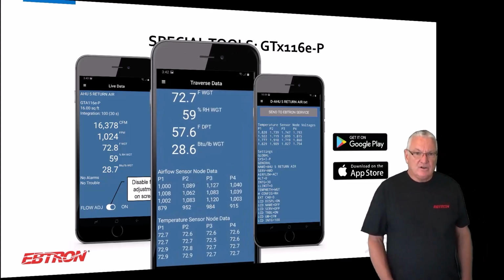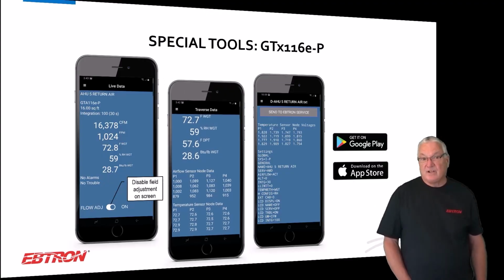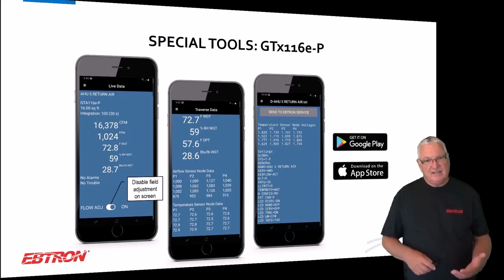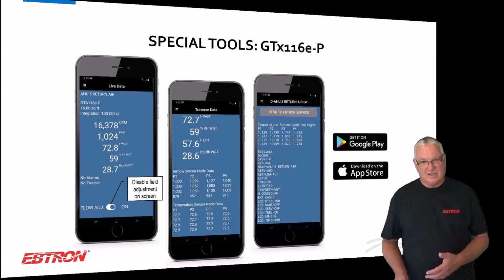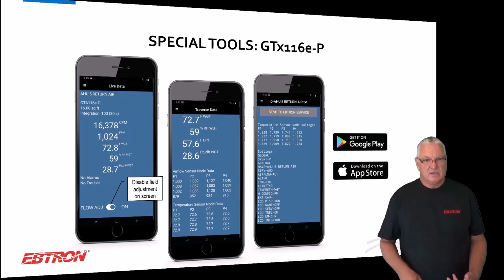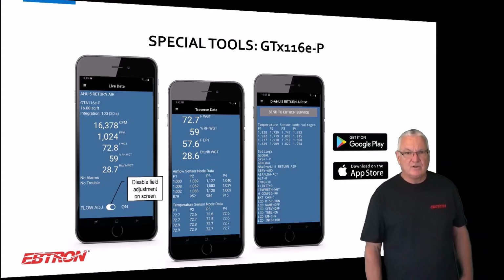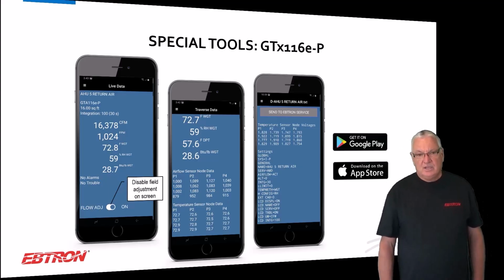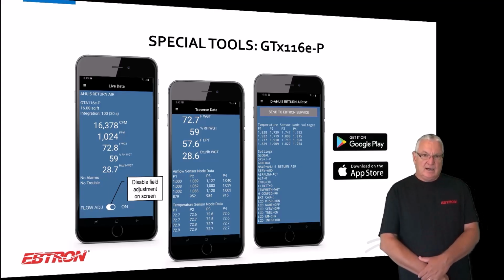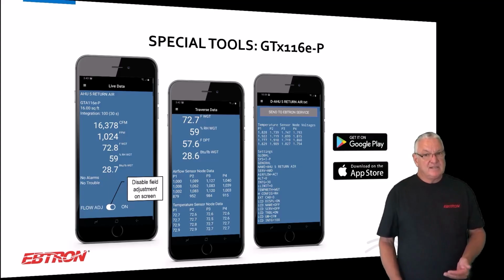Another screen you could go to is this traverse data screen. This was developed for balancers, but it's really a good troubleshooting thing for anybody. You can get the individual airflow rates and temperatures of each sensor node across the network if you were using RS-485 or Ethernet, but also you can get it with this device. Okay, so it'll show you the individual sensor node flow rates and the individual sensor node temperatures, as well as what else is displayed on the screen. You can save this data, you can email this data to yourself.